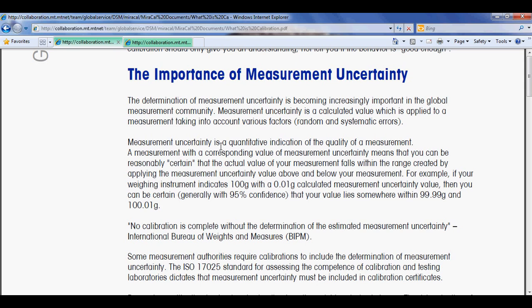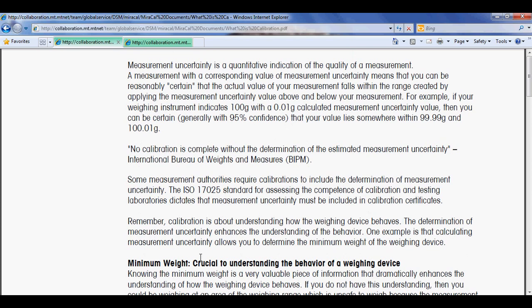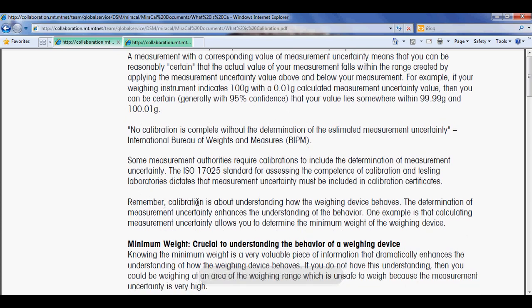Next is a quote that comes from the BIPM, which states that no calibration is complete without the determination of the estimated measurement uncertainty, basically saying that a calibration certificate should always state the measurement uncertainty, otherwise it's incomplete. Some measurement authorities require calibrations to include the determination of measurement uncertainty, and the ISO 17025 standard for assessing the competence of calibration and testing laboratories dictates that measurement uncertainty must be included in calibration certificates. So remember, calibration is all about understanding how the instrument behaves. The determination of measurement uncertainty simply enhances that understanding of the behavior.